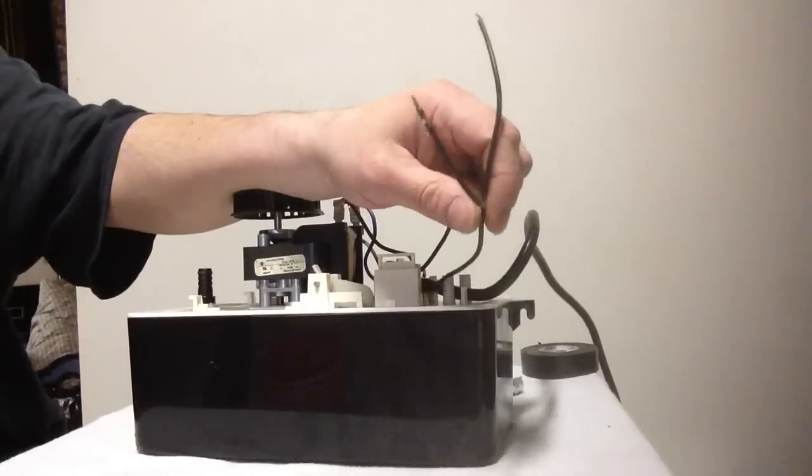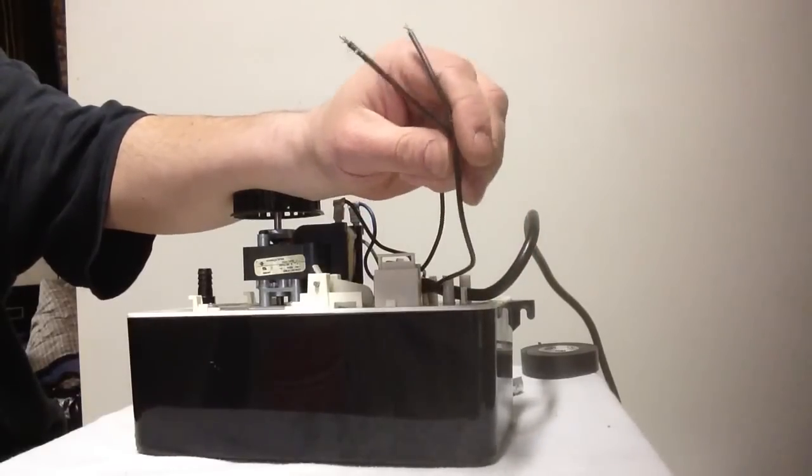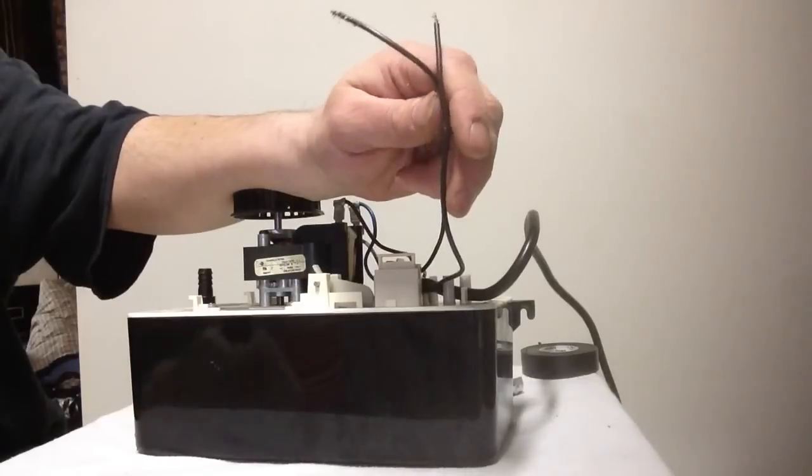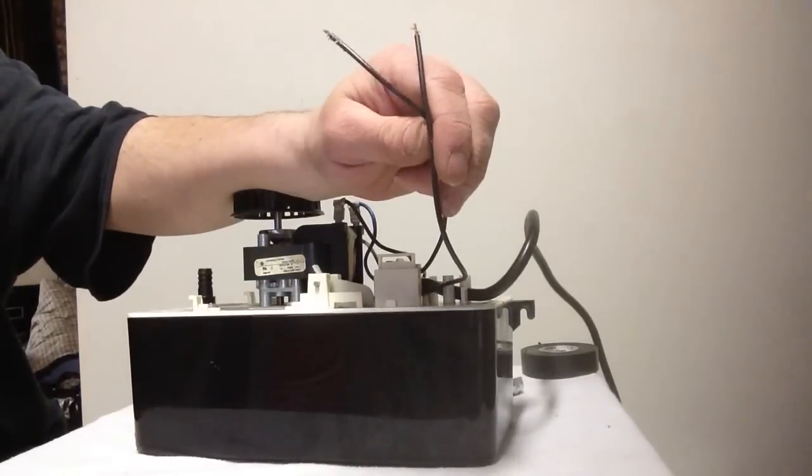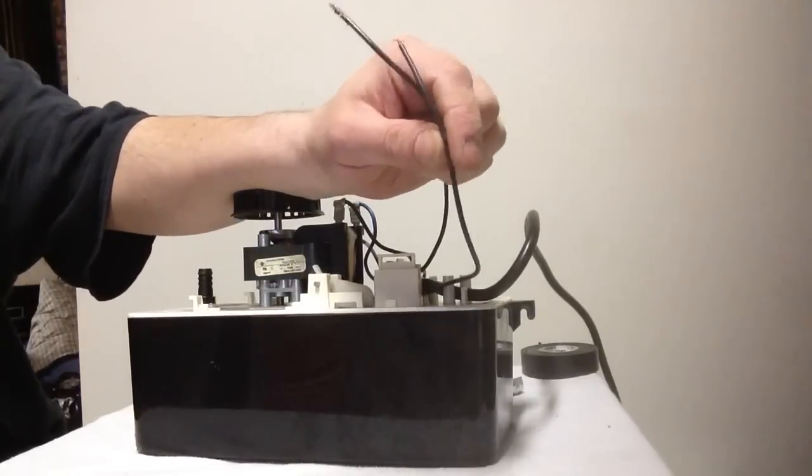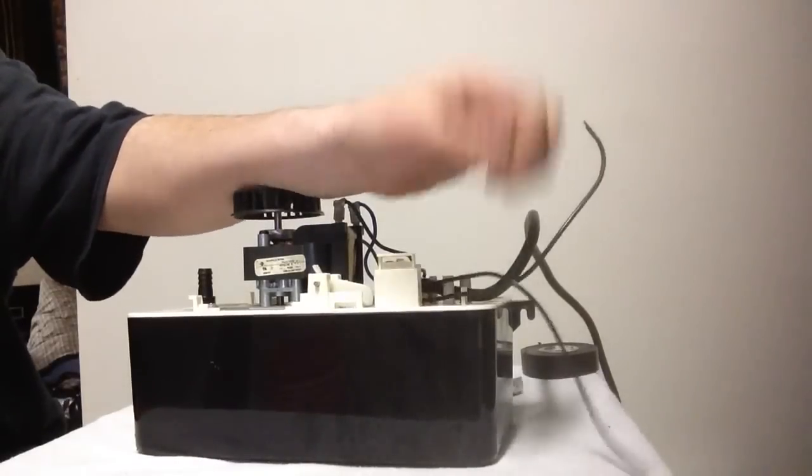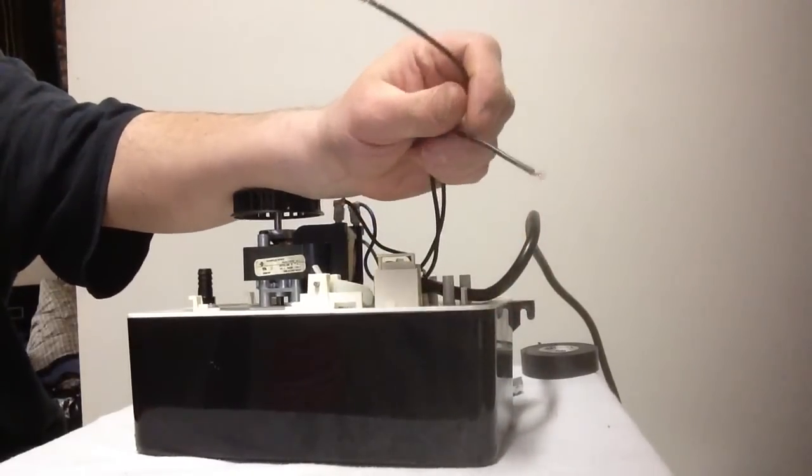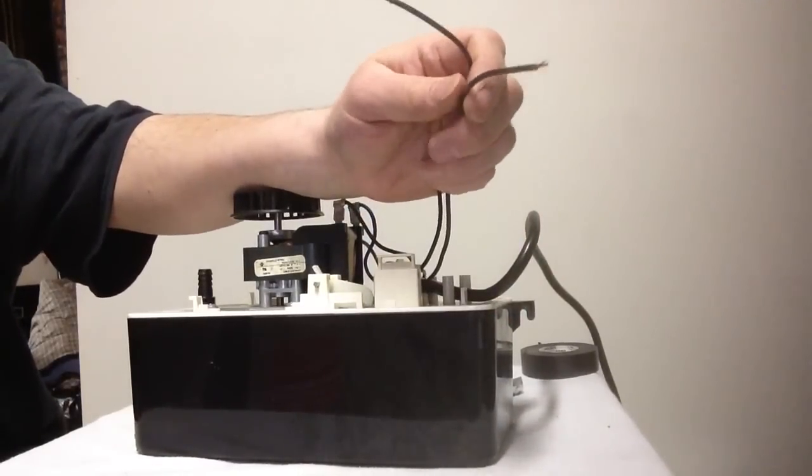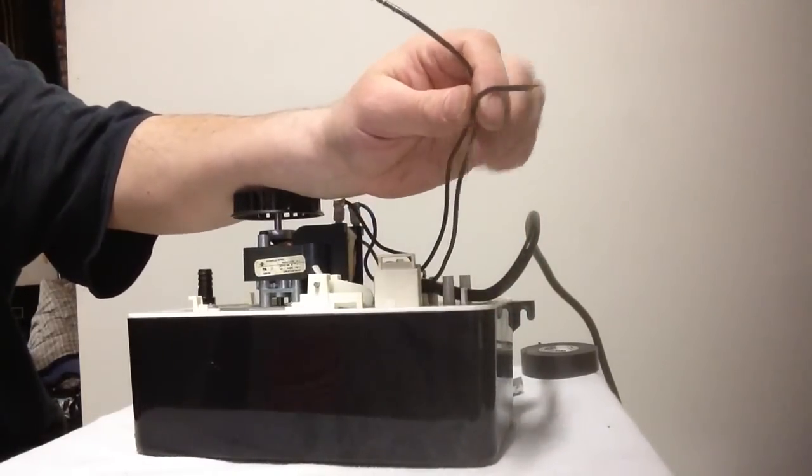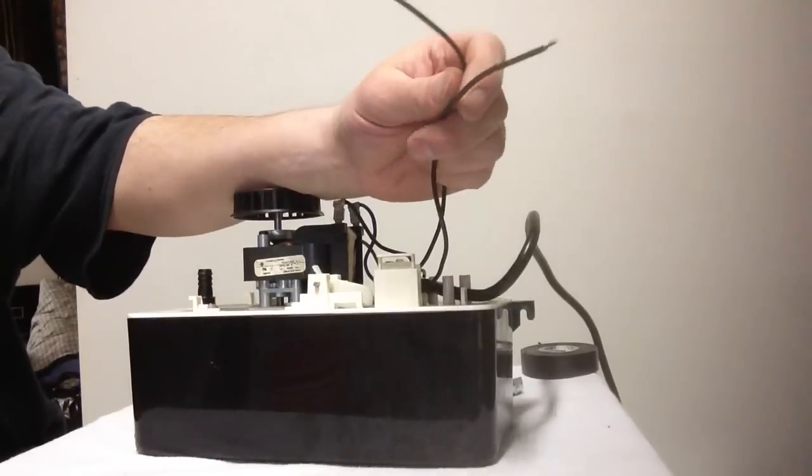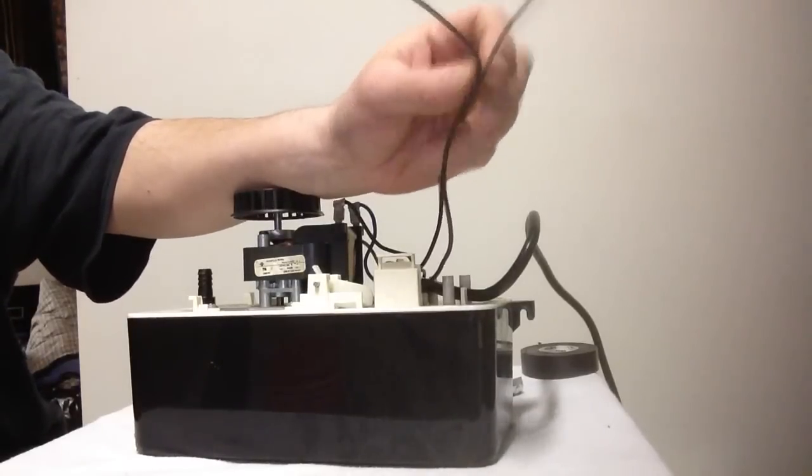If you do that and you're not home for the weekend and the pump fails, it will shut your furnace off and prevent damage. This gets wired into the 24 volt wiring to shut down your furnace.